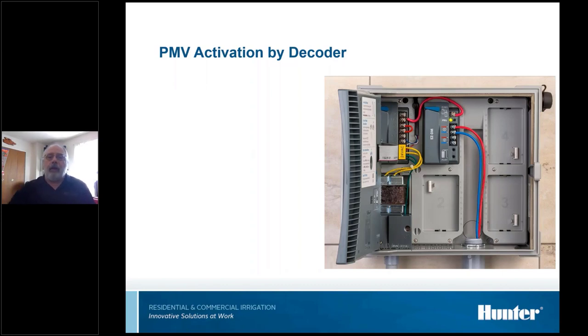So again, a little bit different on Easy when we're doing a pump master valve. If you want the pump master valve to be a decoder, we run a jumper from the PMV output on the module of the controller over to the decoder module and into the PMV terminal on it. When we do that, that tells the module that it needs to send the signal out for the pump master valve on the two-wire path.